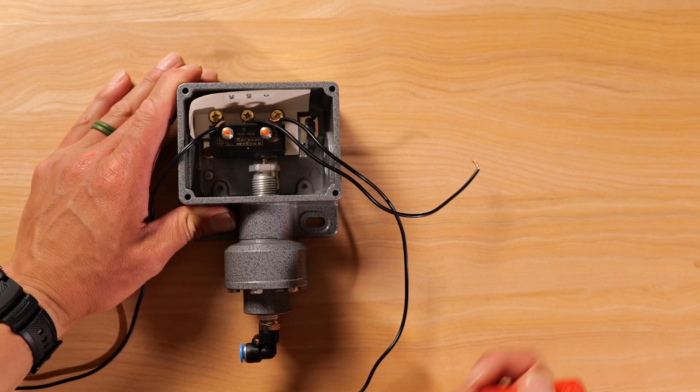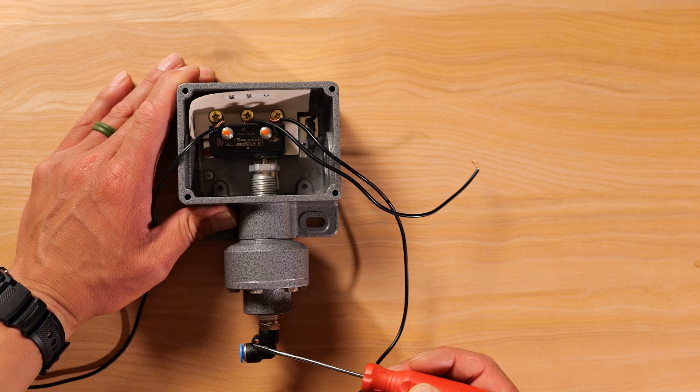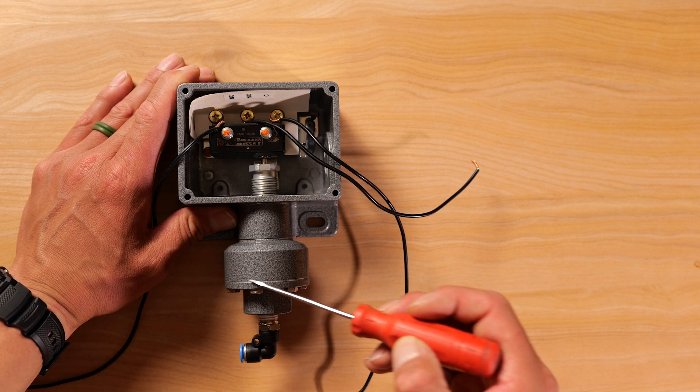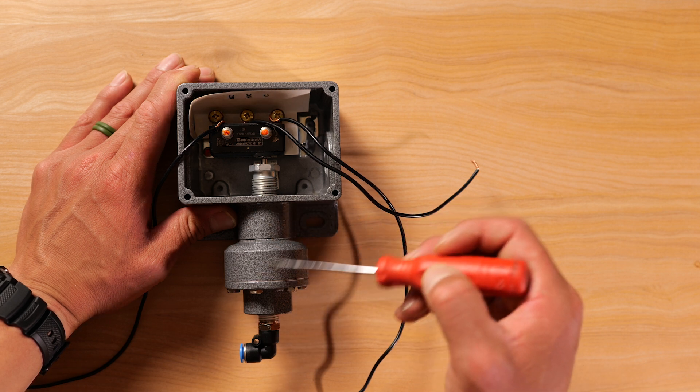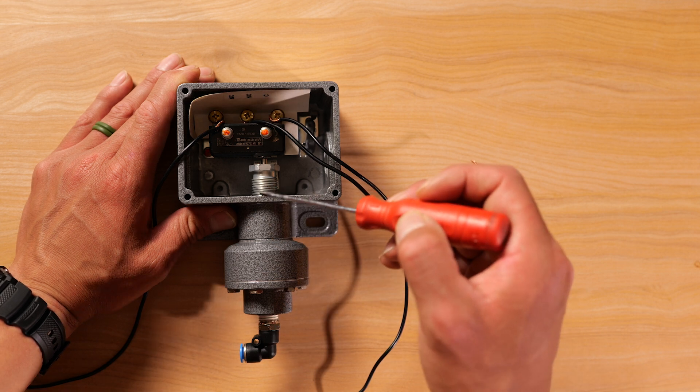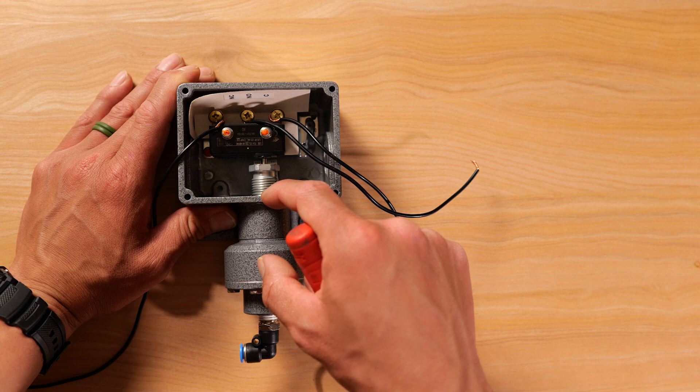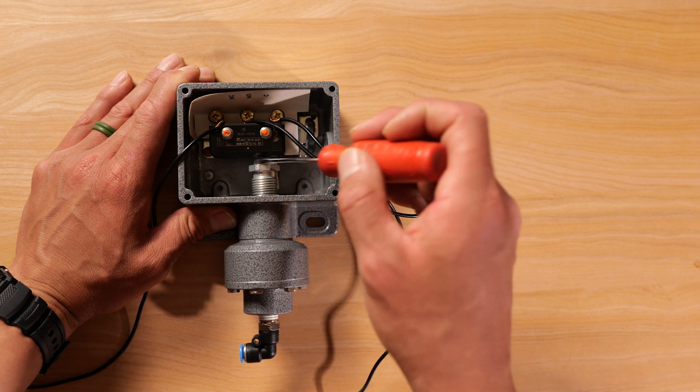All right, so here we have a mechanical pressure switch. Through here you have your process connection. You'll have a diaphragm about right here. You'll have a spring, your range spring here, and the range spring will be adjusted depending on the adjustment screw.